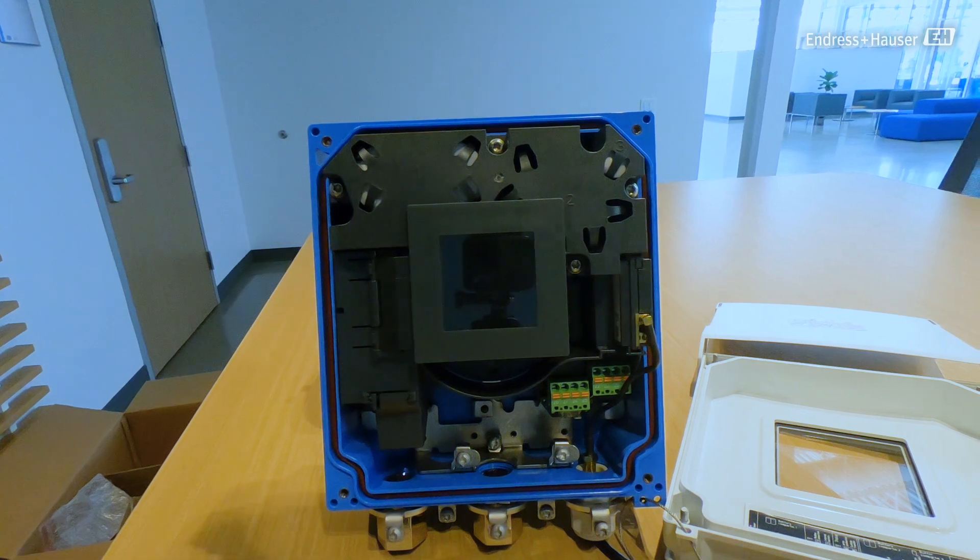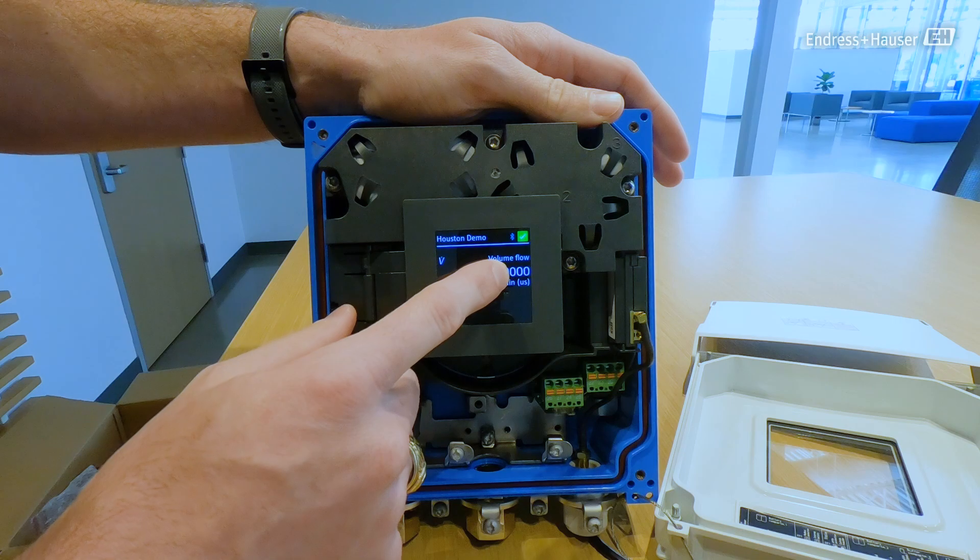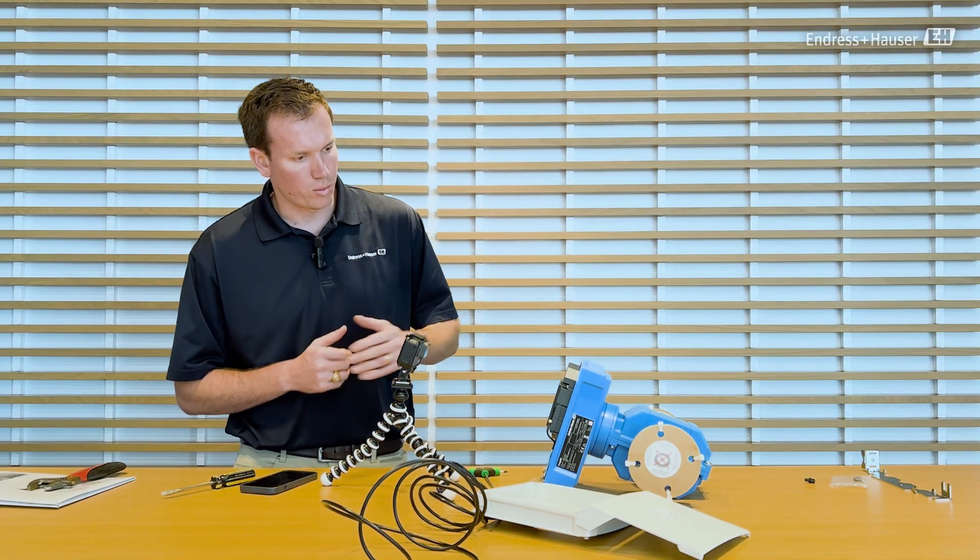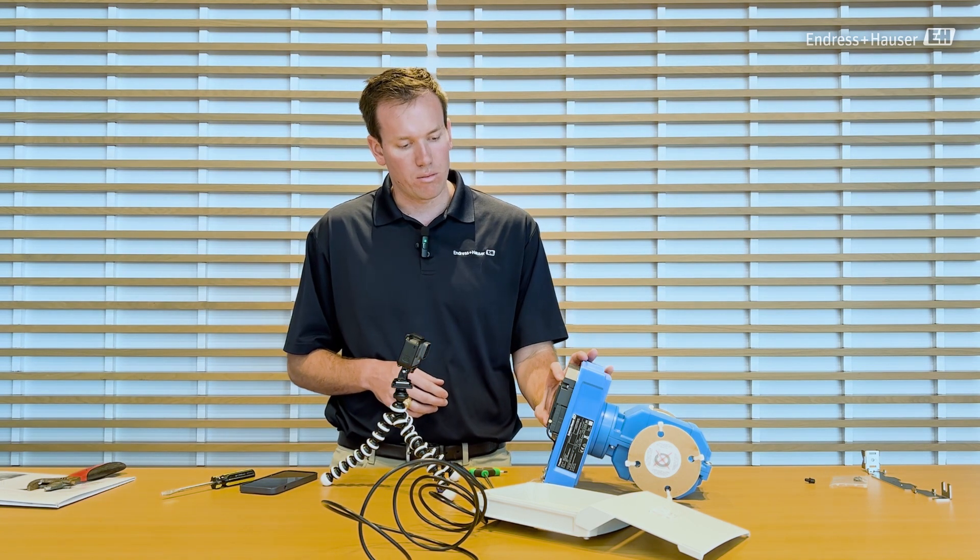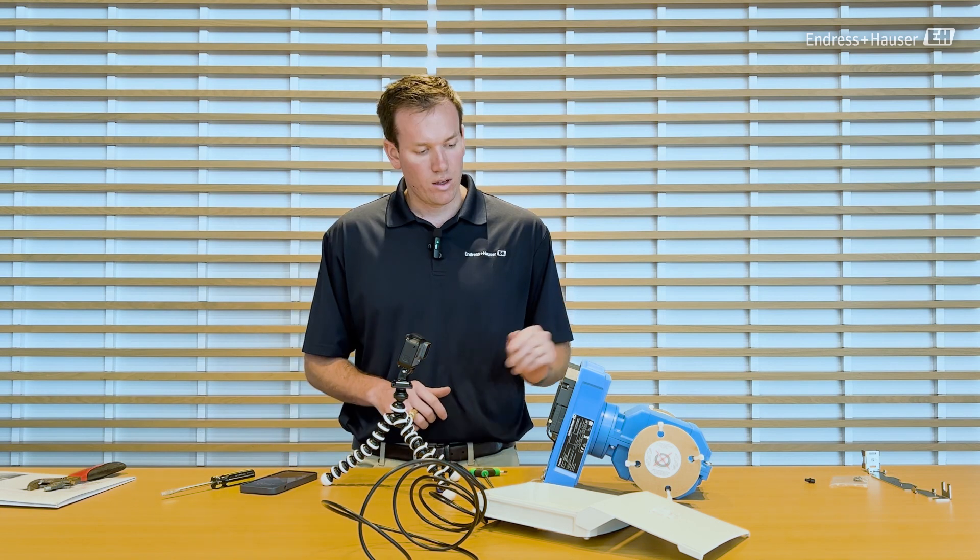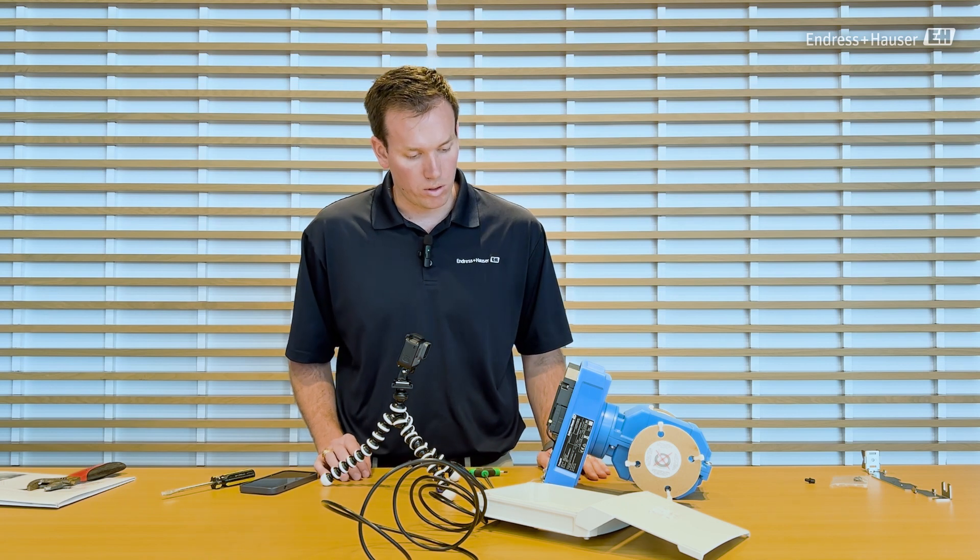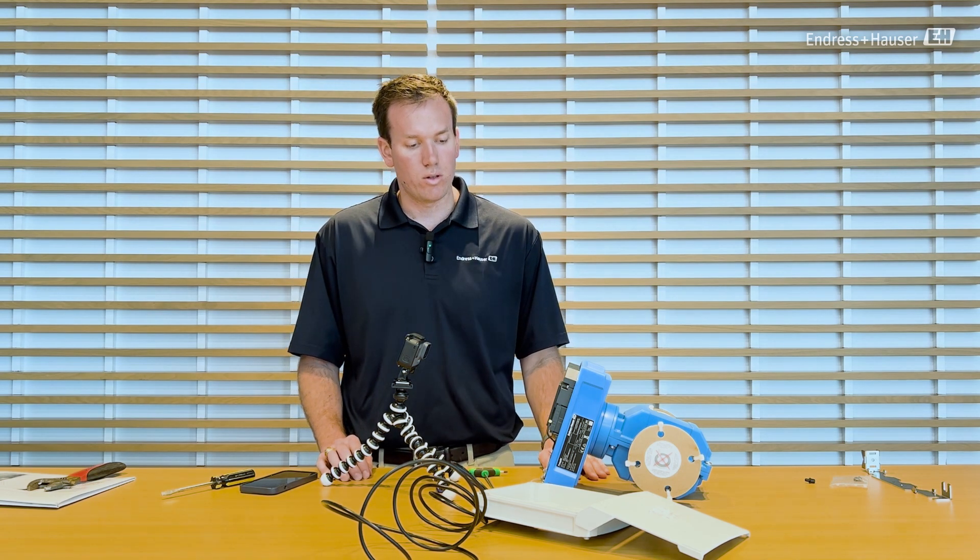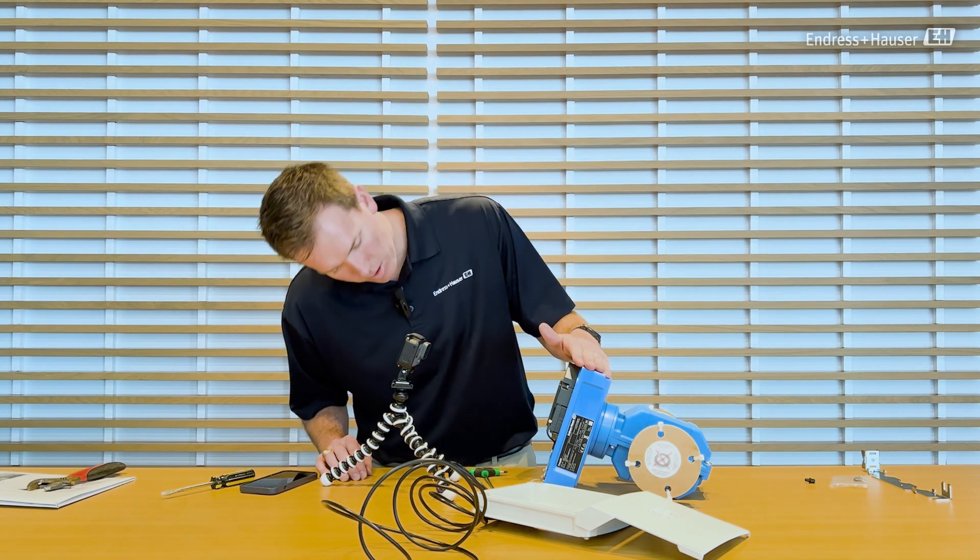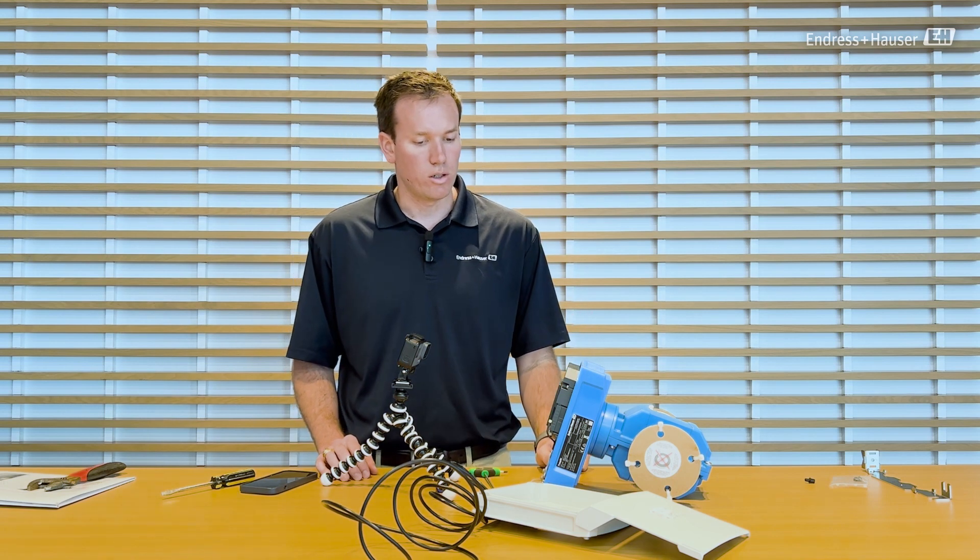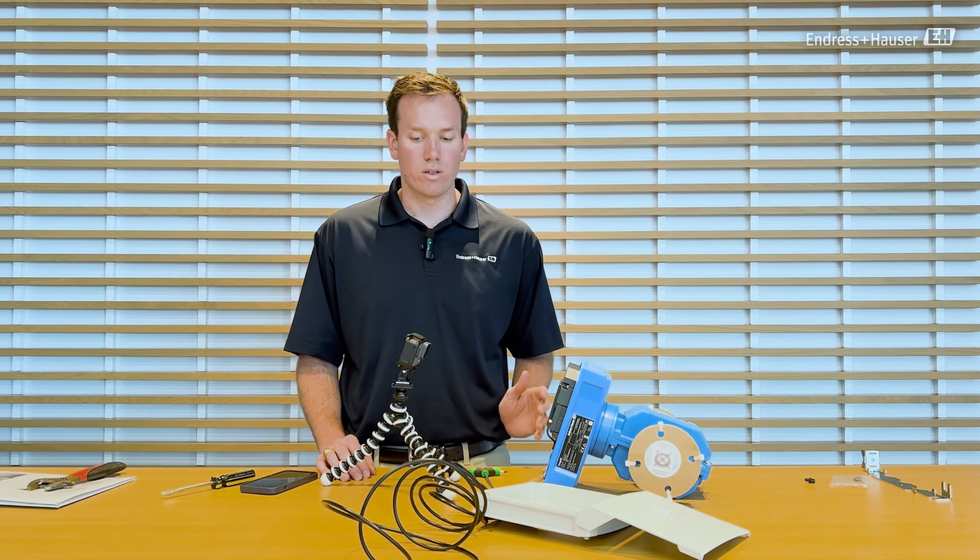The display of this ProMag meter has a touch screen. That touch screen is used to wake it up and show measured values. Normally it's not on, but all of your commissioning setup and interaction of the meter is done using Bluetooth connectivity. You can use a smartphone or tablet. Connect to it using the Endress+Hauser SmartBlue app, which is available on the iOS store or the Google Play and Android store. All of your commissioning is done that way. If you're using a laptop computer, you would need the device care software. The display stays off in normal operation to retain battery.